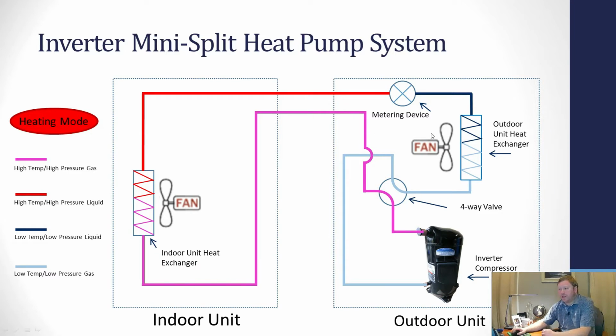So if we're looking at the inverter heat pump cycle, just starting with the compressor, when there's a demand for heat, you're going to have a high pressure, high temperature gas coming off that compressor, just like you would on a regular heat pump. It goes through the outdoor unit reversing valve or four-way valve, whichever terminology you prefer. Following this pink line, that's your hot gas line, it goes to the indoor unit, and then as it goes through the indoor unit heat exchanger, the air from your room blows across that heat exchanger and causes that hot gas to reject its heat and condense into a high temperature, high pressure liquid.